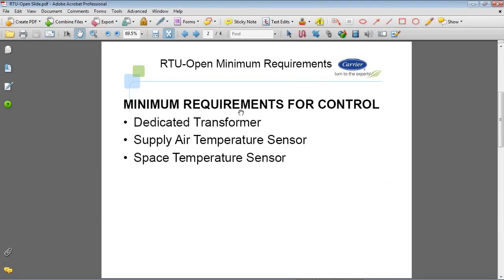The next slide is the minimum requirements that you need for one of these RTU Open controllers if you want to field install it. This comes up a lot, where someone just wants to purchase a controller and throw it on there, but the controller itself cannot function properly unless it has these sensors. All of the Carrier controllers, including this RTU Open controller, require a dedicated transformer. You will lose your warranty if you do not have a dedicated transformer. You need to have one. The controller will not be able to function without a supply air or a space temperature sensor. These two sensors are critical for the logic to actually function.